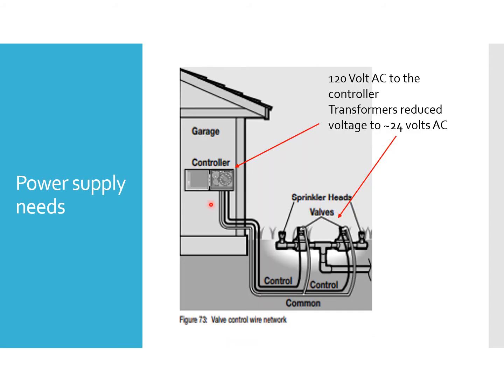This particular controller in this design is an indoor controller, and it's inside of the garage. Its voltage needs are 120 volts AC coming to the controller. The controller will have a transformer either integrated inside of the controller, or the plug that you plug it into the wall is actually a transformer that takes the voltage down to about 24 volts, which is what the irrigation valves are rated at.